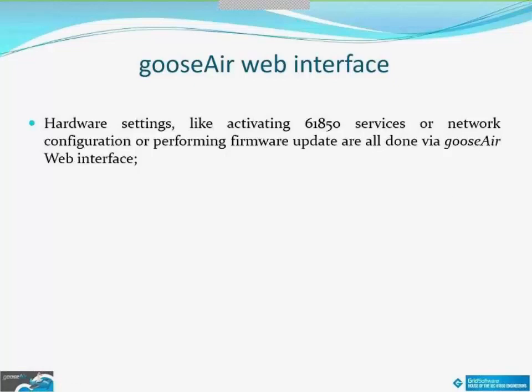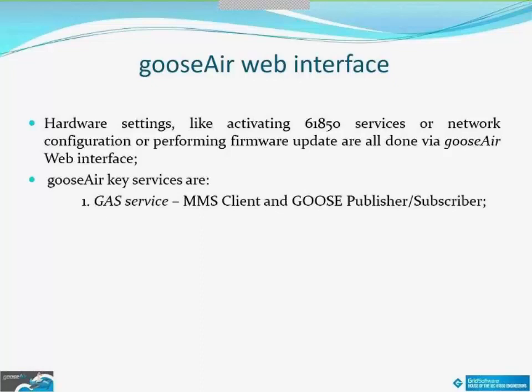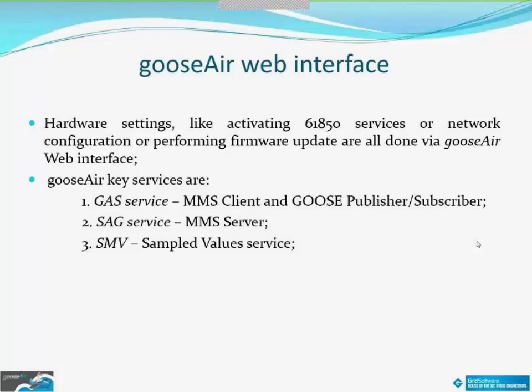So here is a list of key GooseAir services. The GS service, which Samir had mentioned previously, covers MMS client and GOOSE publisher and subscriber services. Then we have an SAG service, which emulates a server in the sense of MMS communication, IEC 61850 server. Then GooseAir supports also SMV service, which covers sample value services, including generating of sample value streams, as well as monitoring and presenting these streams in table or graphical manner.